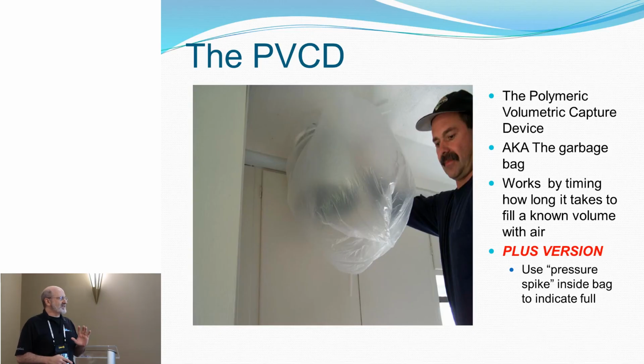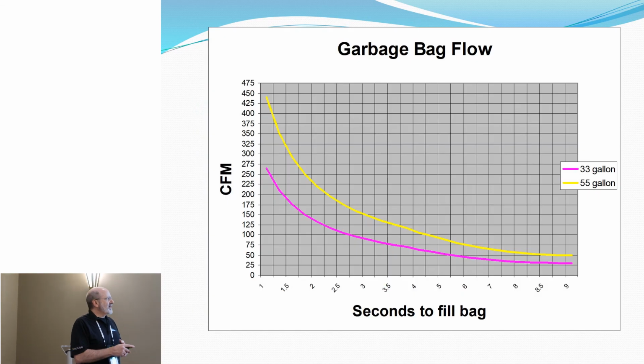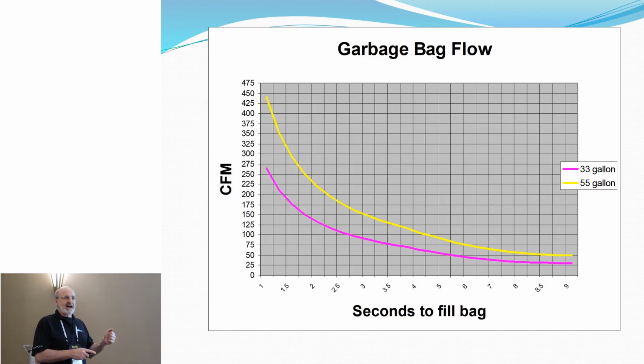I'm going to skip over the bag inflation device. The only thing I want to talk about here is that 3 to 20 seconds, where it comes from, and how rapidly things change if you're trying to use a stopwatch. You can have a change of between almost 200 and 150 or 50 CFM using that bag within a quarter of a second. So if you're using a bag inflation device, pick a bag big enough for your airflow so you're in this transition range. We're starting to level out and you can get a linear number, and it isn't as big a change if you're a little bit off with the stopwatch, if you care to try that. You may even want to try that with a smaller bag in an educational setting with students and say, how quick can you time this? How quickly does the CFM in this bag fill up?